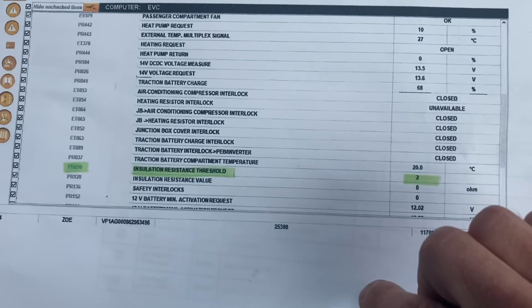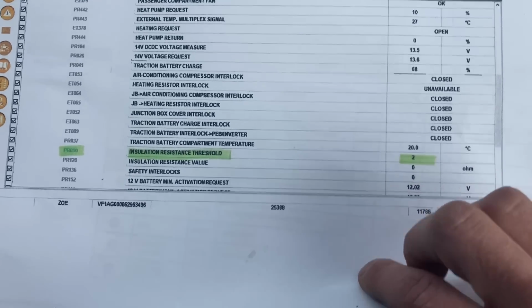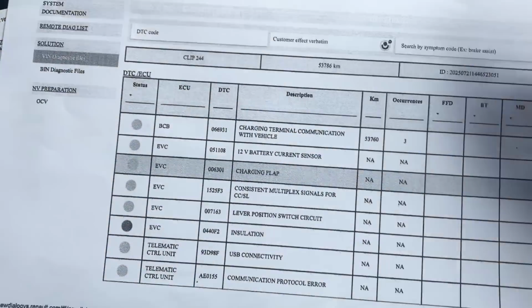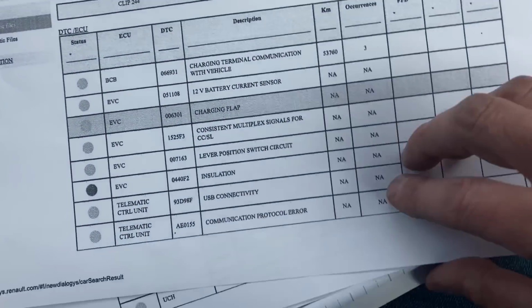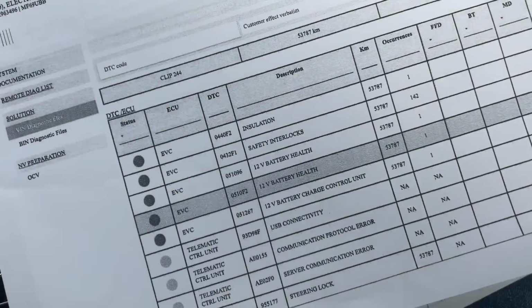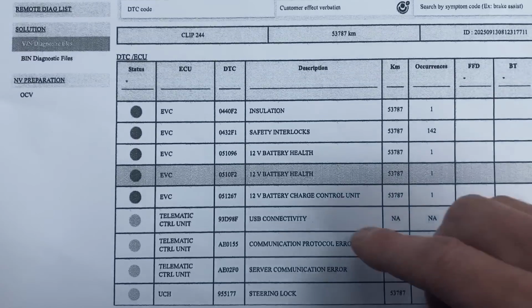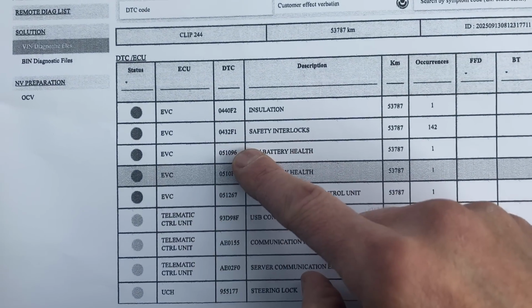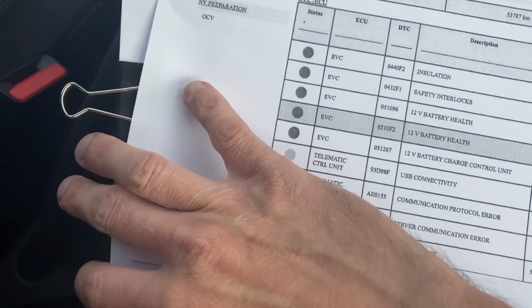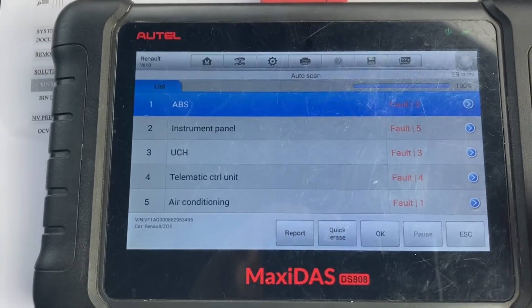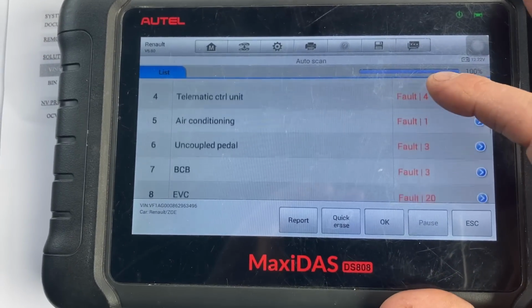So this must be from when it first came in, with just the insulation fault. Then once they'd finished their diagnostics, it was even more broken — now we've got safety interlocks as well. So the interlocks on that sheet are shown as closed, although I don't think that's all of them — we've got some fault codes here.